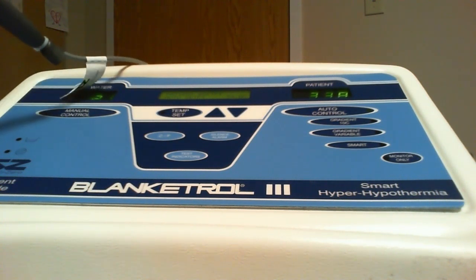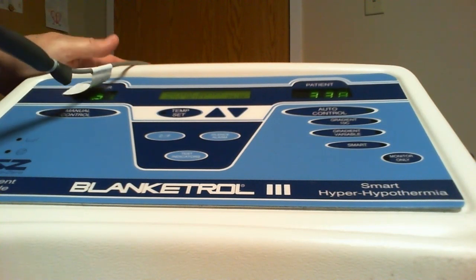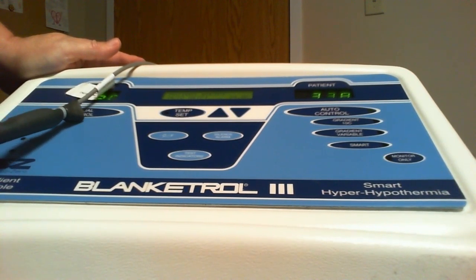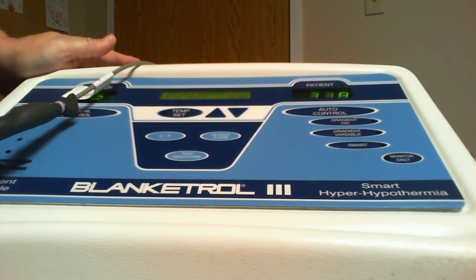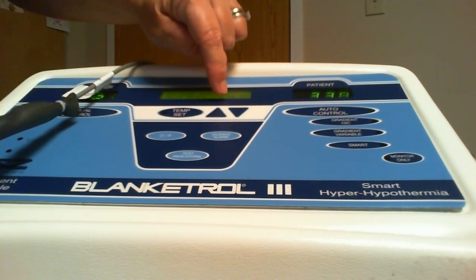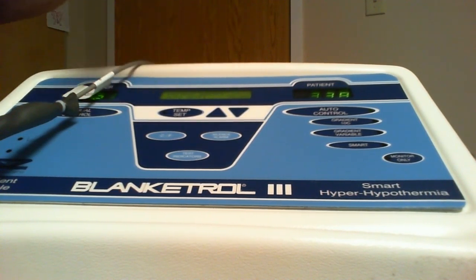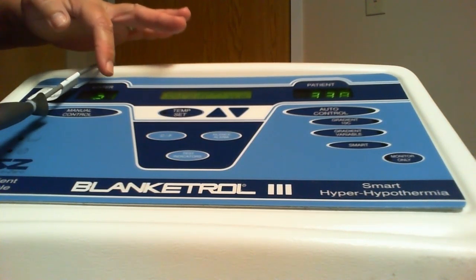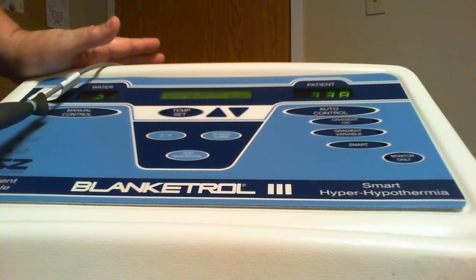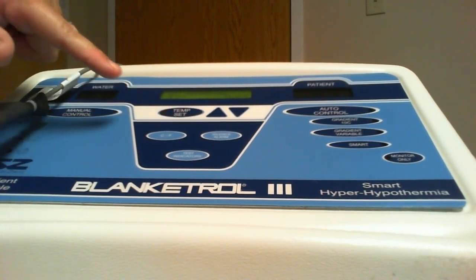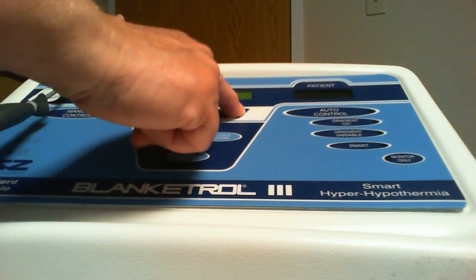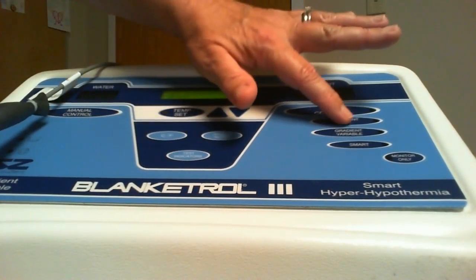And so my patient's temp is 33.8. And very shortly, this blanket is going to recognize that the patient's temperature is below what we have set it at. And it will stop cooling. It won't stop monitoring, but it will stop cooling. The water temperature will no longer drop. So once you have reached, in the auto control mode, once you have reached your targeted temperature, you're going to go to temp set again, and you are going to lower it to 33, because that's where we want our patient to be, right exactly at 33. Then you are going to hit gradient 10, smart mode.